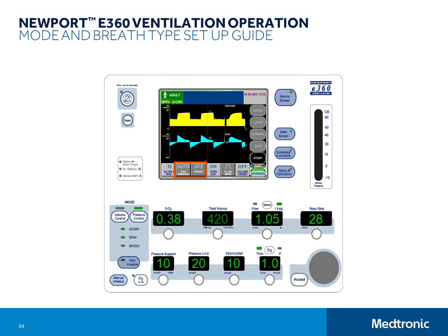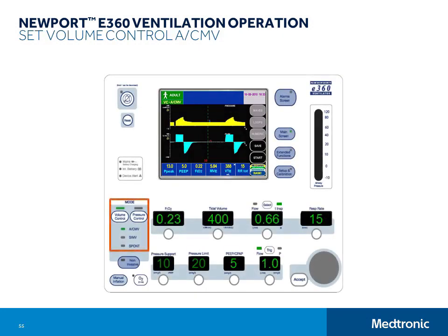We'll start with volume control ACMV. Set the breath type mode selector to volume control ACMV. You do this by pressing the volume control button until ACMV is lit, then pressing accept. When you are ventilating, you will see that the breath type and mode is displayed in the upper left corner of the GUI. This means it will appear in the screens that you save and download as well. Use the touch turn accept method for all other settings.